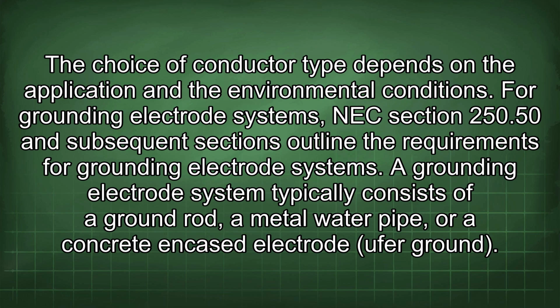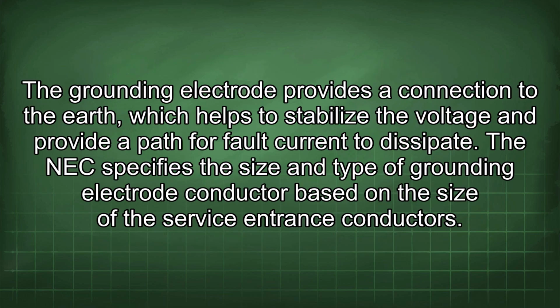For grounding electrode systems, NEC section 250.50 and subsequent sections outline the requirements for grounding electrode systems. A grounding electrode system typically consists of a ground rod, a metal water pipe, or a concrete encased electrode (ufer ground). The grounding electrode provides a connection to the earth, which helps to stabilize the voltage and provide a path for fault current to dissipate. The NEC specifies the size and type of grounding electrode conductor based on the size of the service entrance conductors.